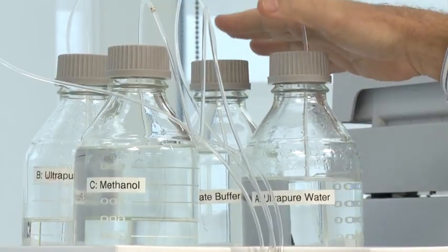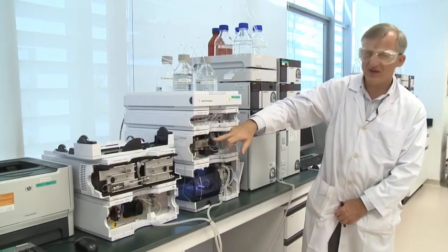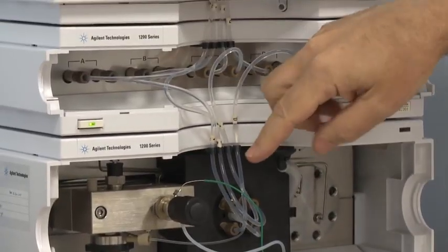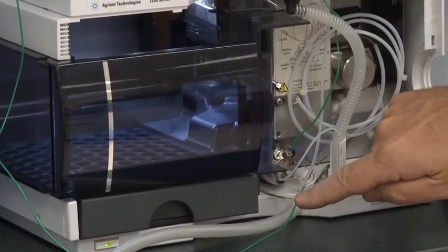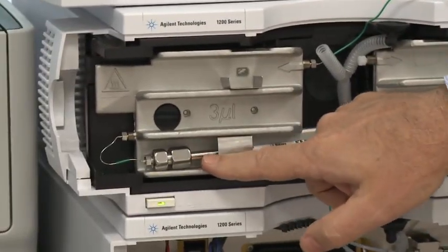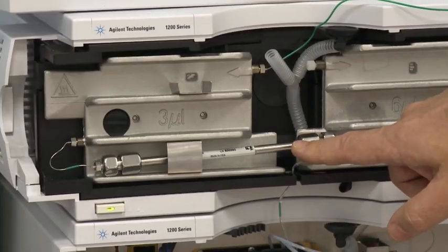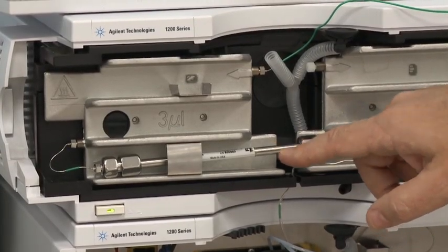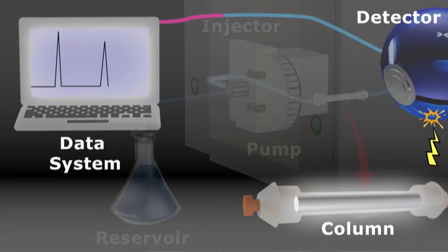Okay, this is an HPLC instrument. On the top here, we have the different components that mix together to make the mobile phase in these bottles. Here we have the pump that pumps the mobile phase through the instrument and provides the pressure. The sample is injected into the system, once again by an autosampler. It then travels along this very fine tube here to this part of the instrument, and here we have the column. And you can see the HPLC column is quite different to the GC column. This is made of steel, and the pressure inside is currently 157 bar. The sample passes through the column and then passes to the detector, and the information from the detector is fed to the computer, and again it can be displayed and recorded.